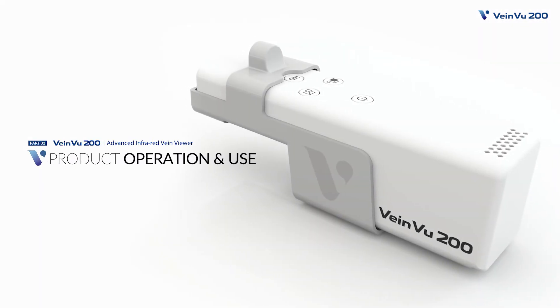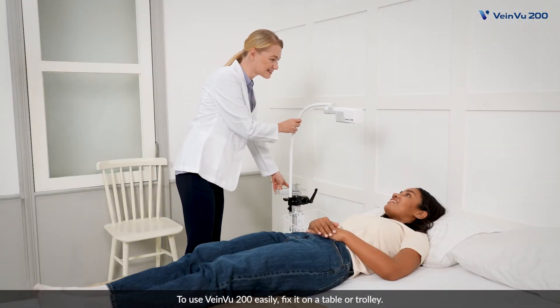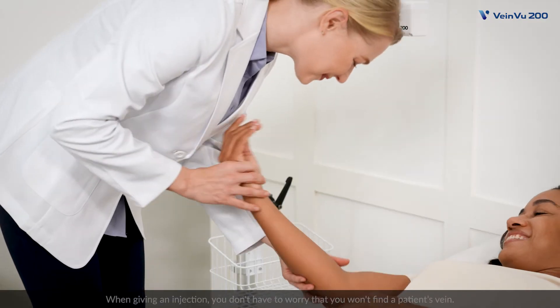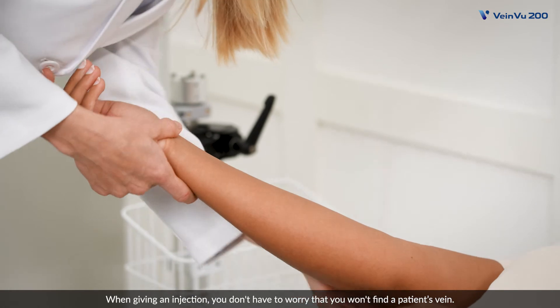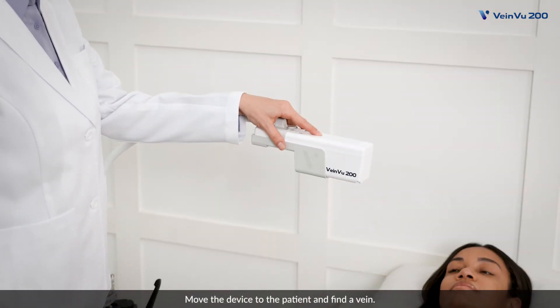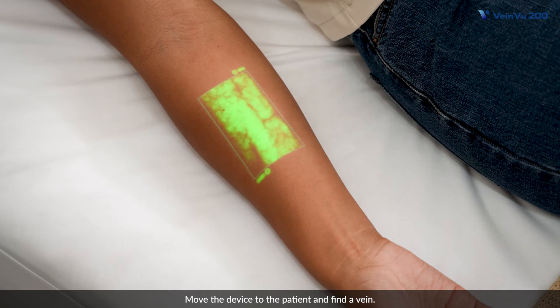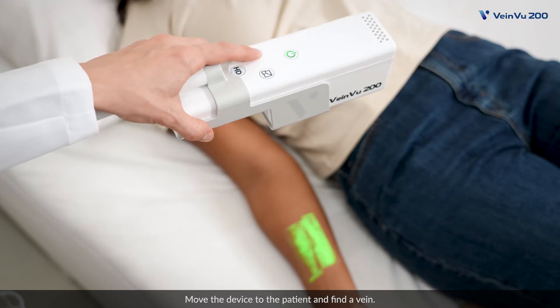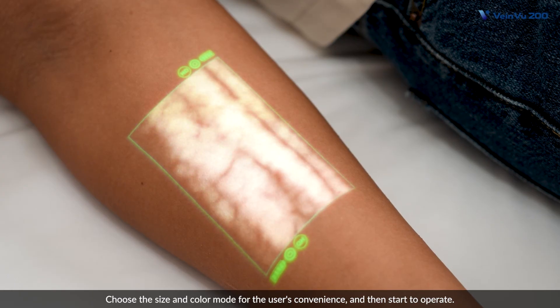To use VeinVu 200 easily, fix it on a table or trolley. When giving an injection, you don't have to worry that you won't find a patient's vein. Move the device to the patient and find a vein. Choose the size and color mode for the user's convenience and then start to operate.